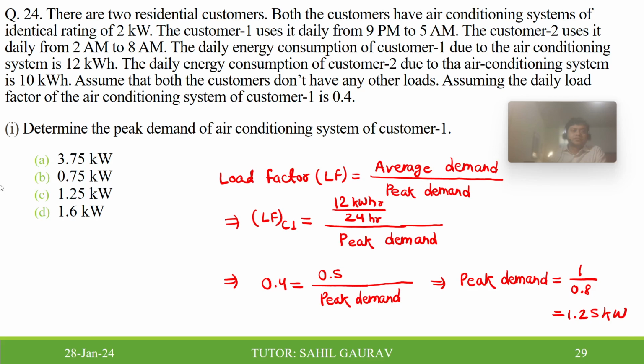So you have to go step by step. The first part is to find the peak demand. The load factor of customer one is given as 0.4, and the average demand we can find from here. The daily energy consumption of customer one due to the air conditioning system is 12 kilowatt hour. So the average demand is 12 kilowatt hour divided by 24 hour, which gives 0.5. From there the peak demand comes as 1.25 kilowatt. So there is nothing new in this problem.